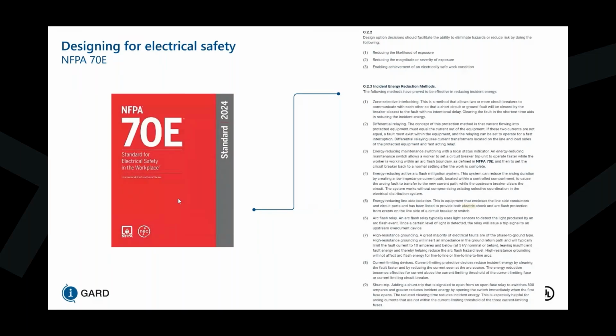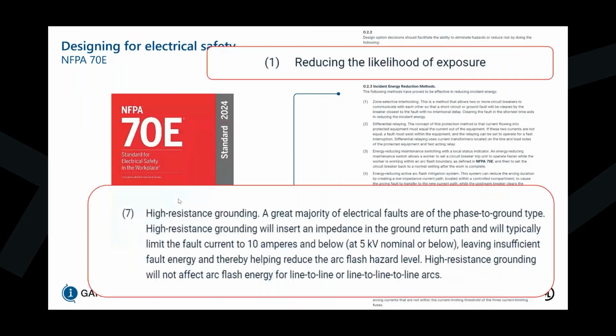Of the 9 listed, high resistance grounding is the only one reducing the likelihood of exposure, whereas all the other incident energy reduction methods are acting after the fact that the arc is already in the system and it's looking to trip the upstream protection once the arc has been detected. Whereas with high resistance grounding, we're placing that resistor at the neutral point to ground already in advance of any phase to ground fault. And then when a phase to ground fault occurs, it leaves insufficient fault energy and helps reduce the arc flash hazard level by clamping that current to a value of 10 amps or less.